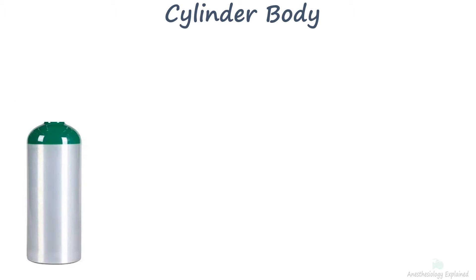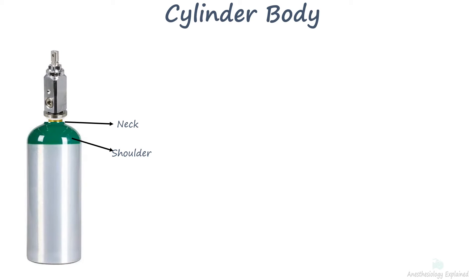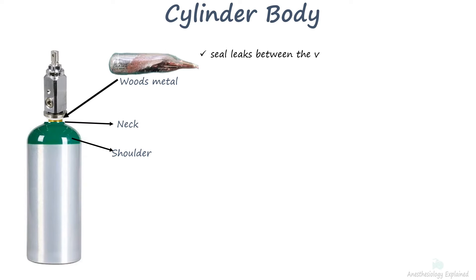The curved upper part of the body is called the shoulder, which tapers into a neck. The neck ends in a tapered screw thread into which the valve is fitted. When the valve is screwed to the cylinder neck, a fusible material called Wood's metal is used to seal leaks between the valve and the cylinder.